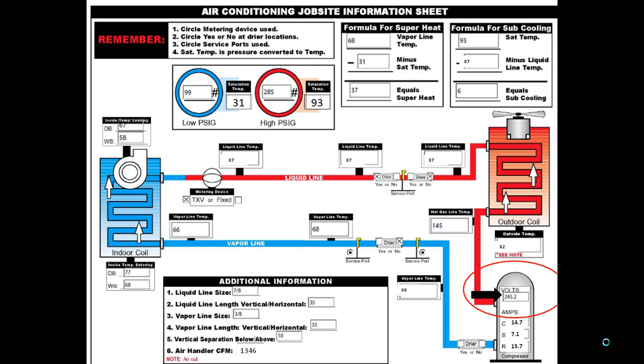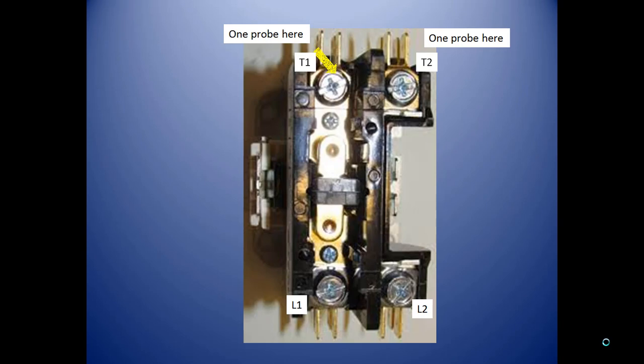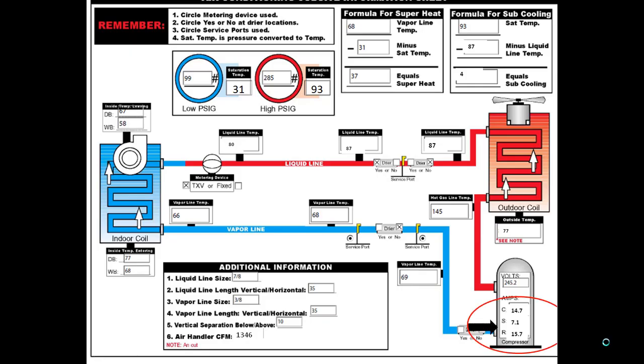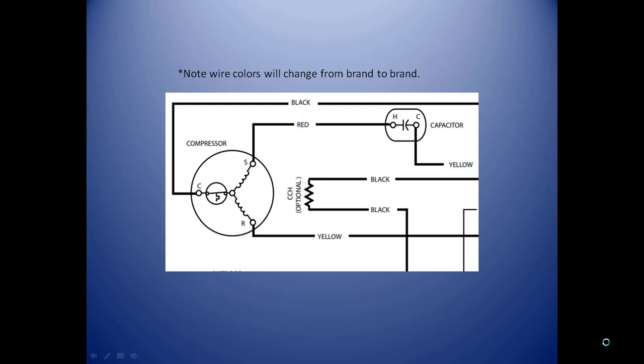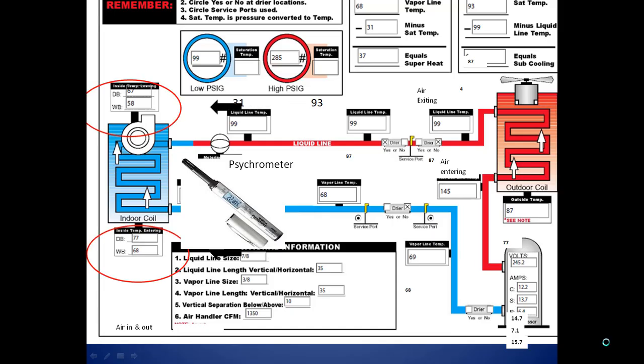Moving on to voltage readings, we need to get the voltage and amp draw on the unit. Take the voltage reading on T1 and T2 of the contactor. Amp reading, we'll move on to the compressor. Start, run, common wires. Just take note that the colors on these wires from brand to brand do change. We need the temperature readings entering and leaving, both wet bulb and dry bulb, on our air handler. That can be taken there with a psychrometer like you see in the picture. Also, in and out air on the condenser.